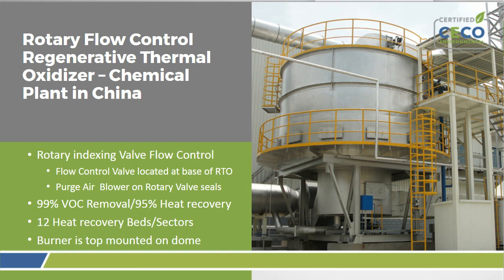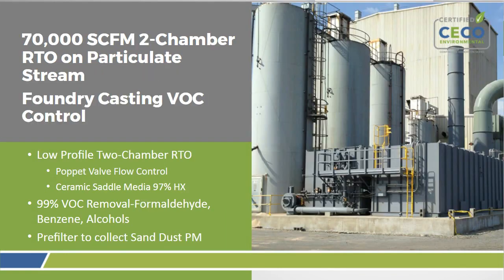There's 12 heat recovery sectors. If you looked at a top plan view, it looks like cutting a piece of pie or a round pizza into 12 shapes. So that gets 99% destruction and 95% heat recovery. This is a low profile unit, typically even on larger sizes, this one is 70,000 CFM. It's on a particulate stream, so there are reverse air dust collectors ahead of it. It's on a foundry casting line, so you will get some sand dust that does carry through. So formaldehydes, benzene, alcohols, that's typically what this application is seeing.